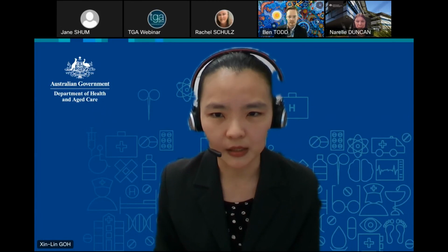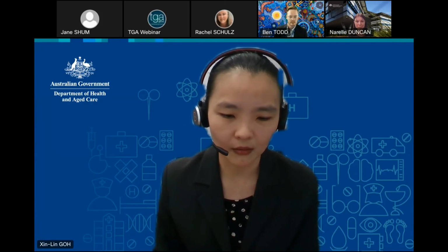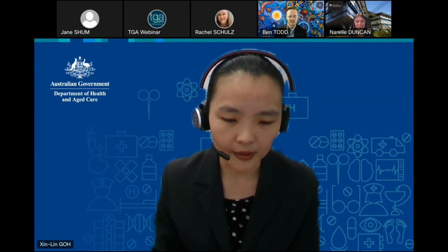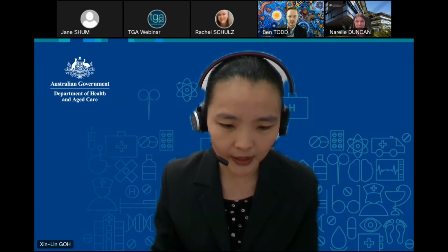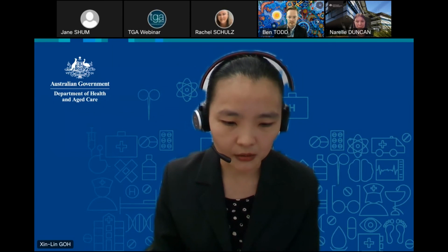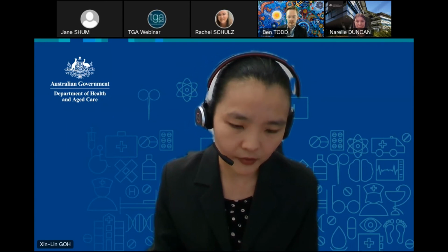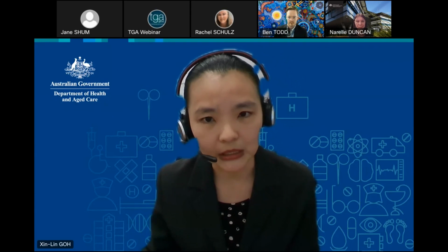So once again, the end date of the MDD certification is May 2024, and there may be devices who receive MDR certification after this date. And depending on whether there is a gap in certification or whether the manufacturer does not intend to seek certification thereafter, in the second situation where the manufacturer does not intend to seek certification thereafter, they have 12 months to exhaust the MDD stock.